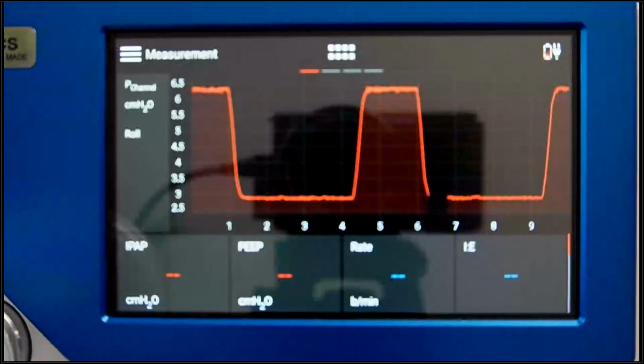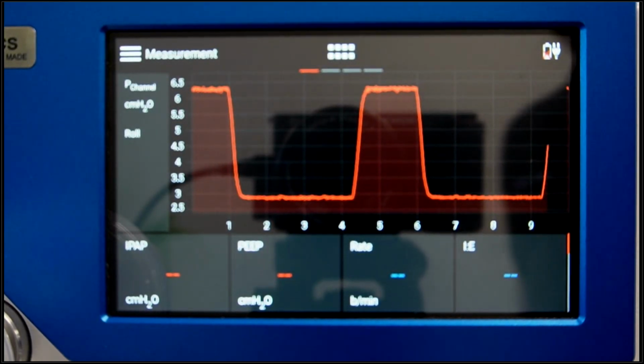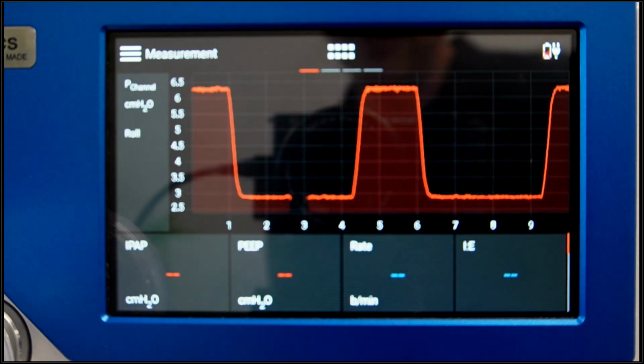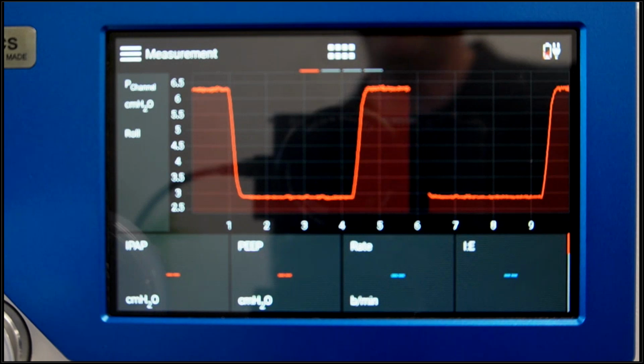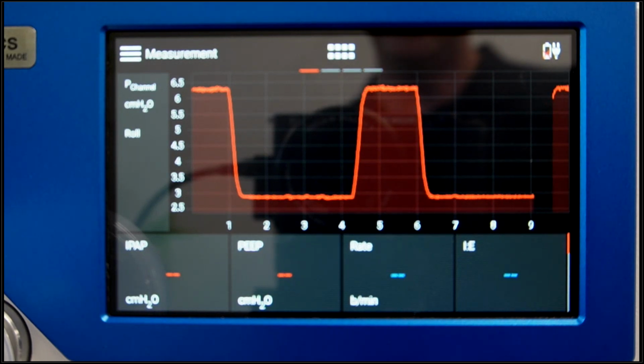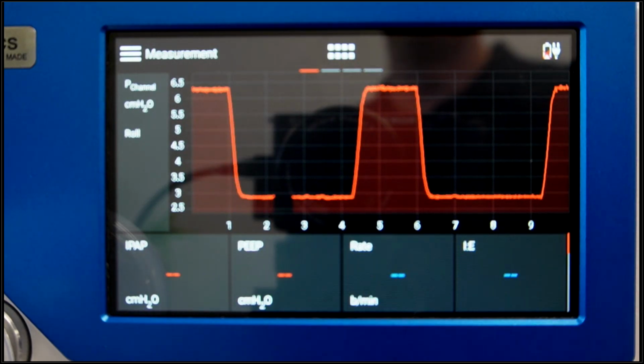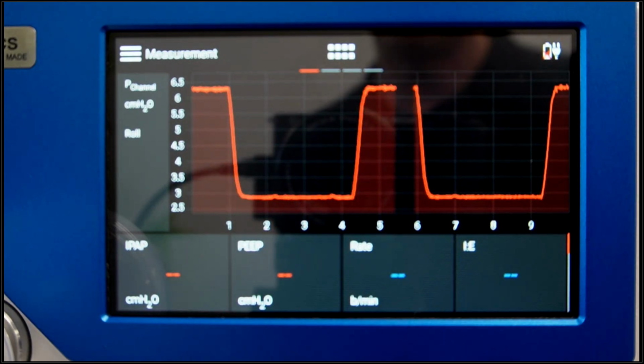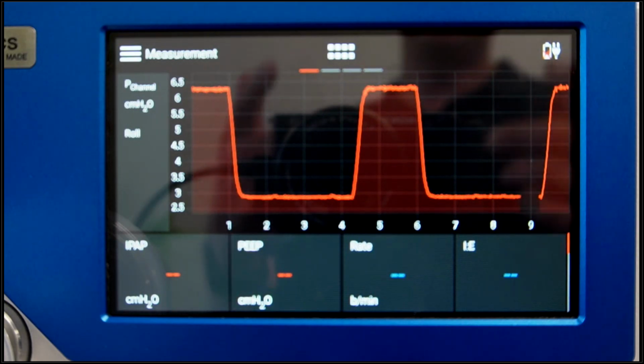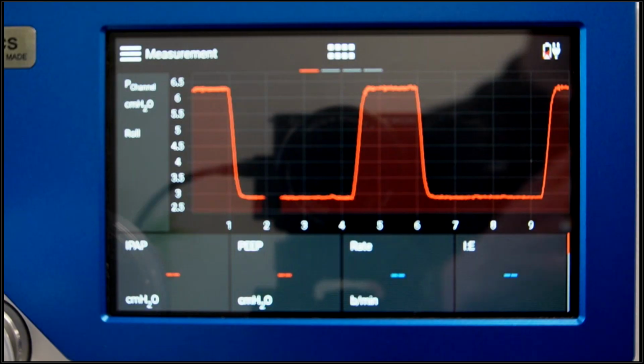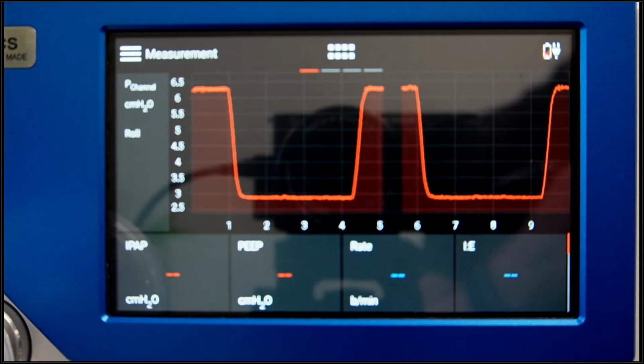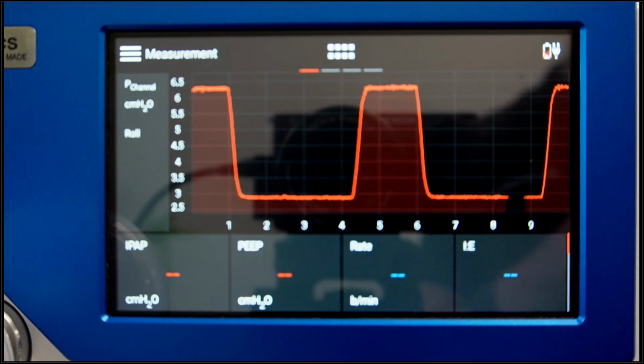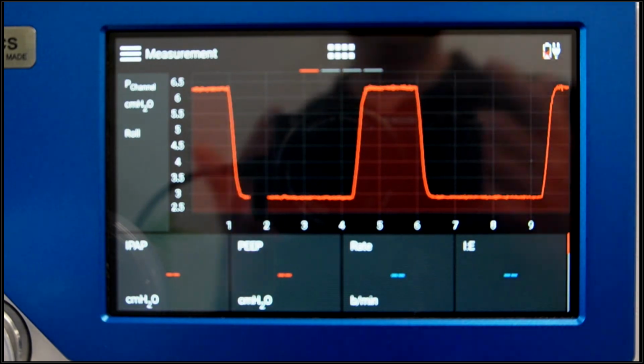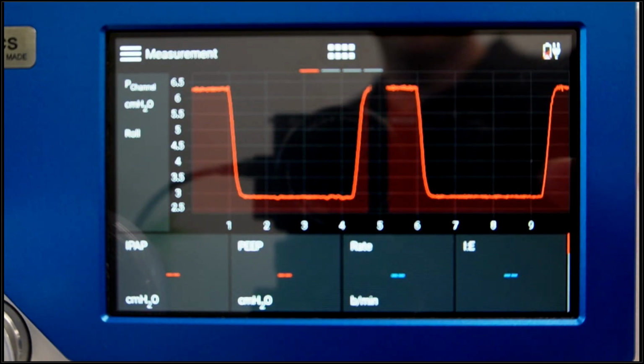So now let's have a look at our gas flow analyzer. So I'm going to change the camera again. We can see the display of our gas flow analyzer. You can see the settings I have now on my ventilator: an EPAP of 3 centimeters of water and an IPAP of 6. And as you can see right now, my analyzer is not able to measure the breath-based parameters, for example, IPAP rate and I/E ratio. This is because right now I'm running on the default trigger settings that we have discussed earlier, that are based on a negative and positive flow through my device, which I don't have in my situation here. So here, as we've learned, we would use the pressure curve and set our triggers.